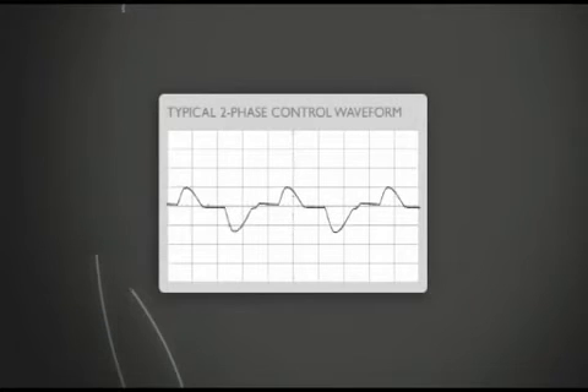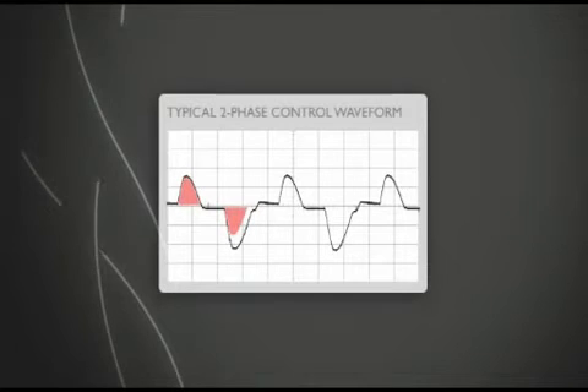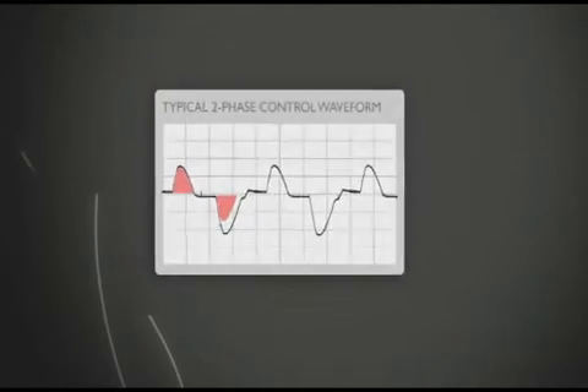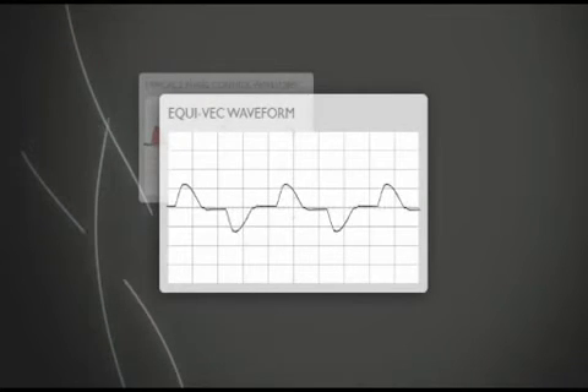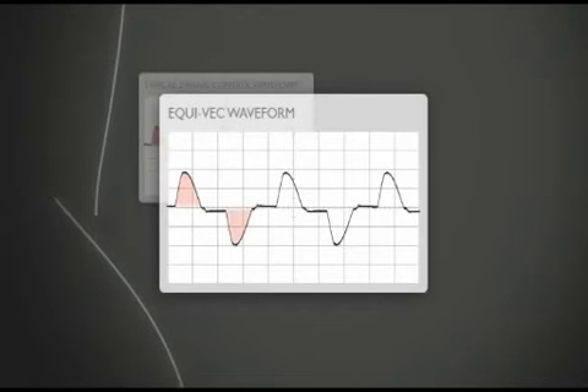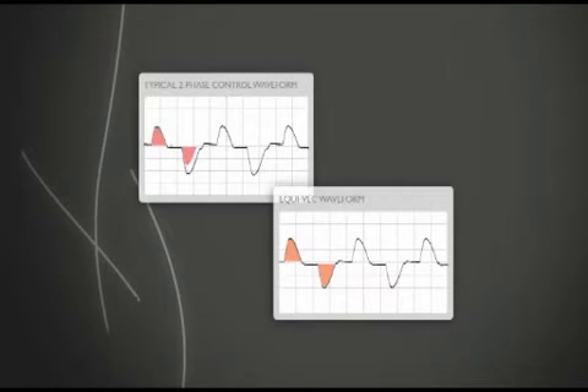Some soft starters use two-phase control that generates asymmetrical waveforms, which causes extra heat in the motor and requires higher starting current. The CSX controls only two phases but includes AuCom's Equivec balanced vector control technology. By balancing the waveform, the CSX provides three-phase performance with compact soft starter technology.